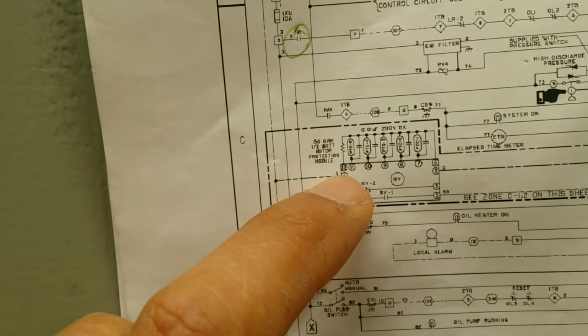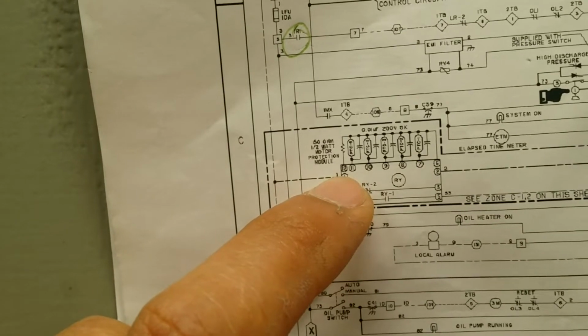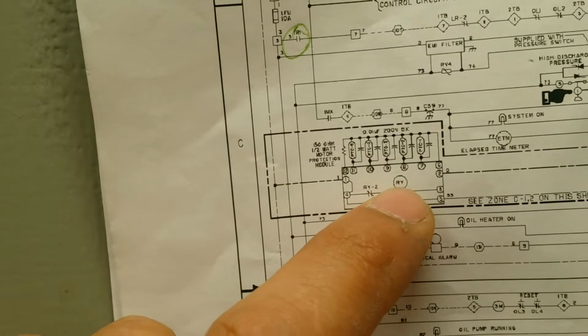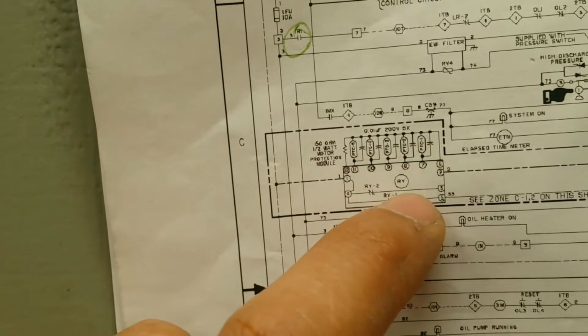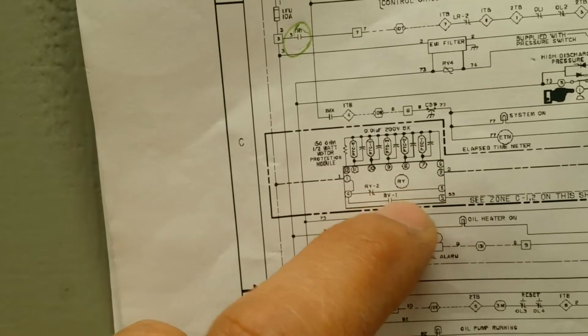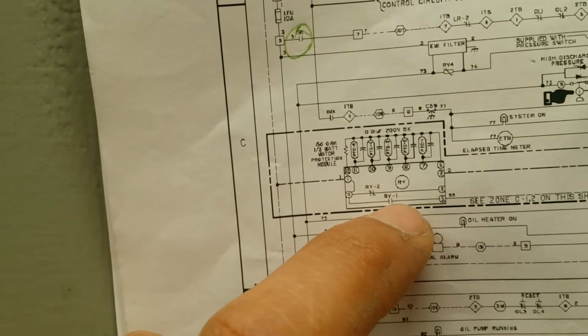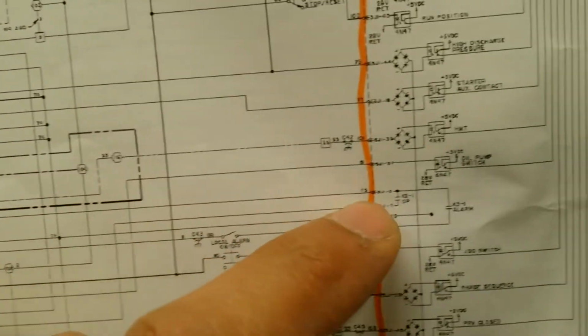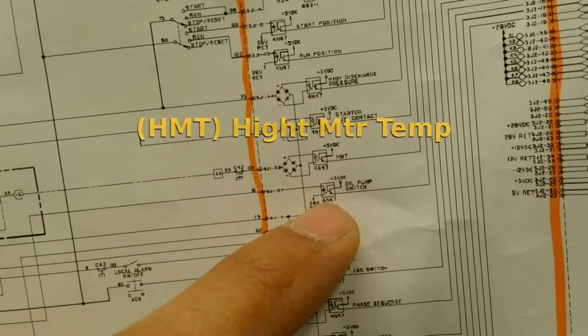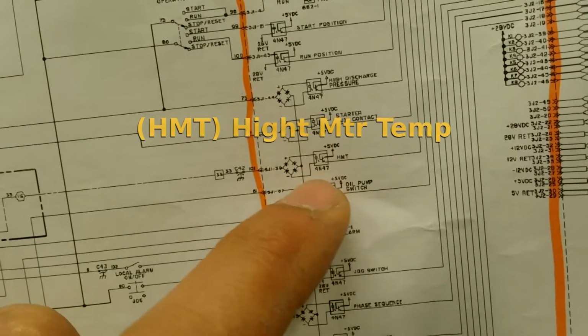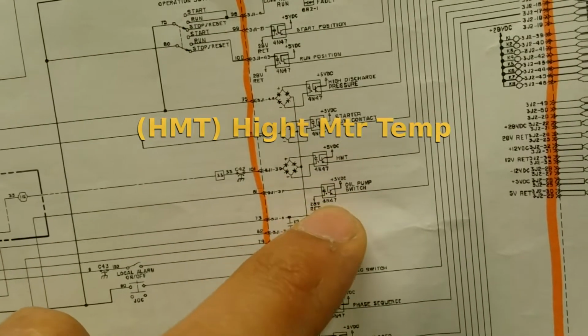There is no way that you can change the thermistor in the field if a thermistor goes bad, and there is a PMS card for all these too. So as long as all of these inputs are right, this relay will be energized, and this set of contacts RY-1 will be energized, and that is required to provide an input. This input right here is one of the requirements for the system to be able to start. So never neglect to check to ensure that this relay is closed whenever you're troubleshooting that your system doesn't want to start.